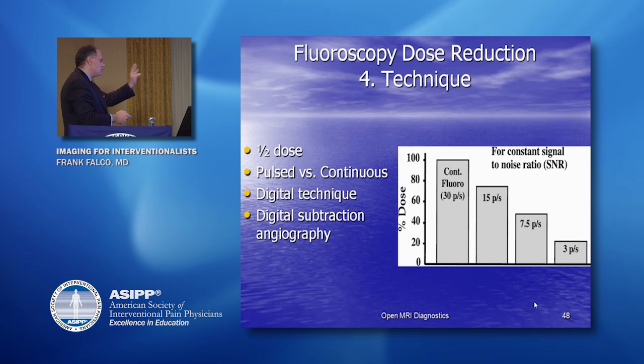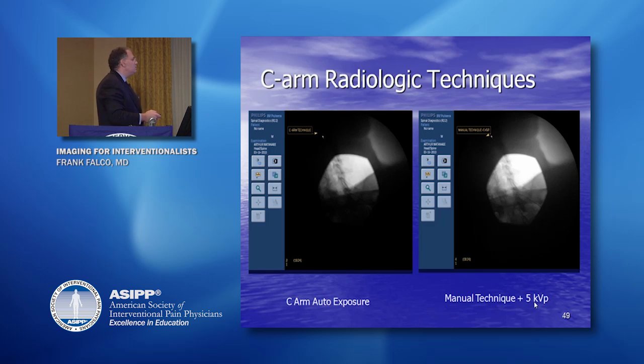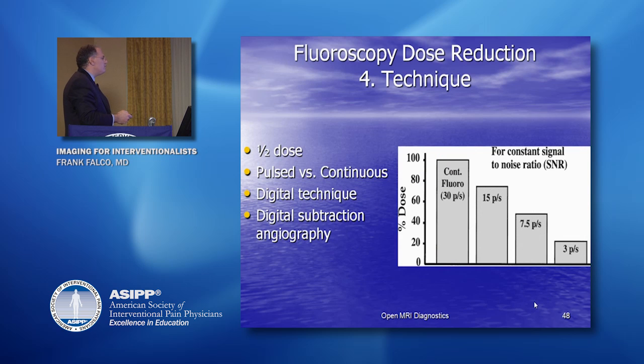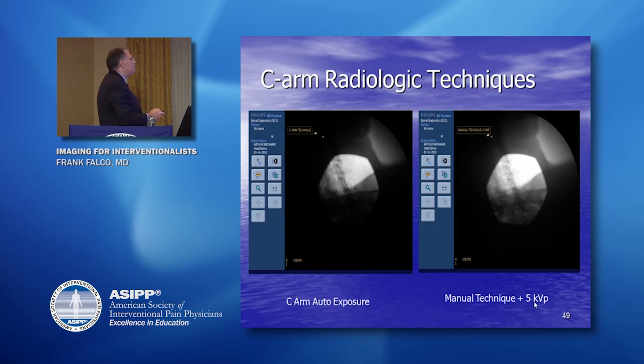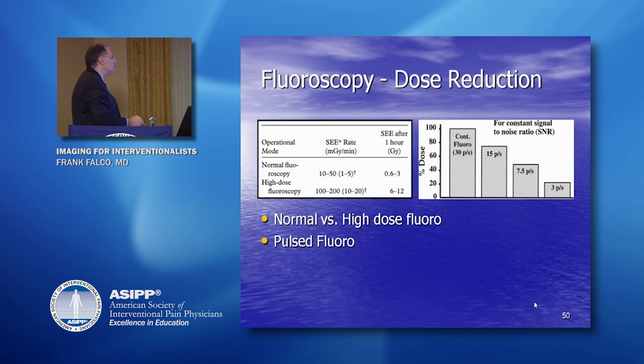Fluoroscopic dose reduction. We talked about pulse versus continuous digital technique and digital subtraction angiography, which all affect the signal to noise ratio. Here we see some collimation, again trying to target our area so we get less exposure and better clarity of our image. Normal versus high dose fluoro: high dose fluoro gives you more exposure, but it can help to reduce your noise and get a better picture, particularly with large people.